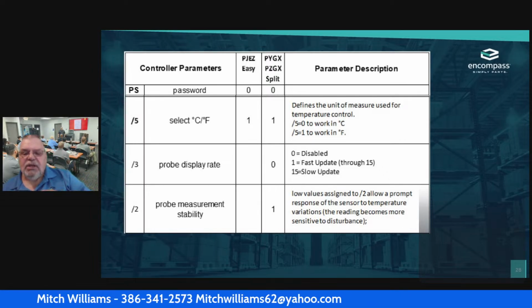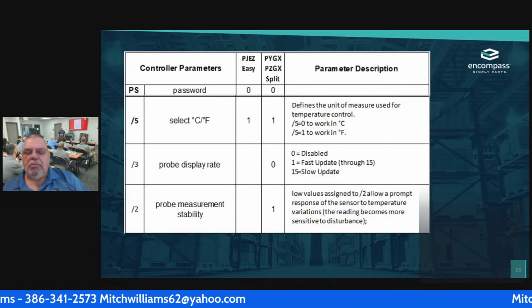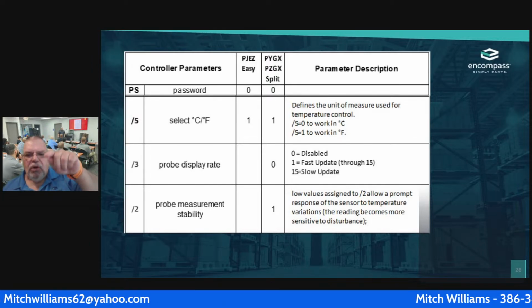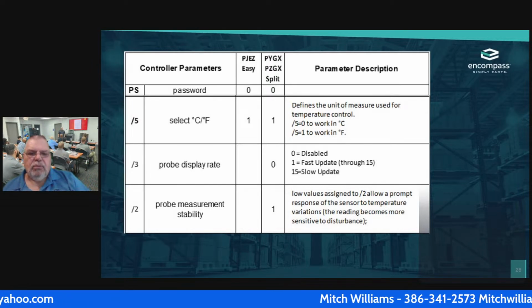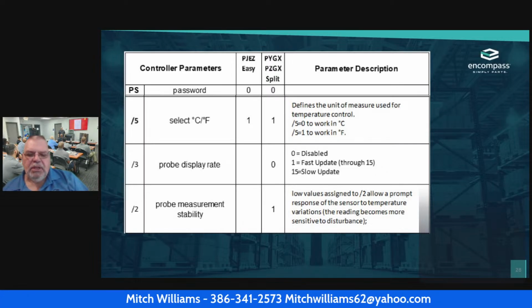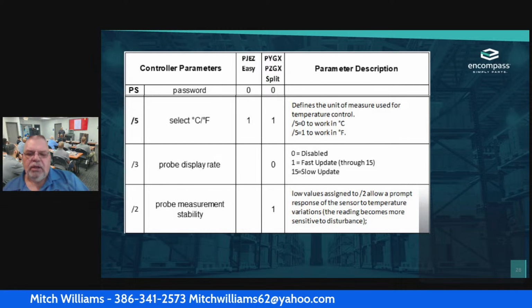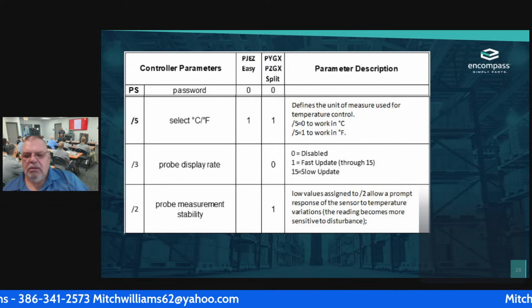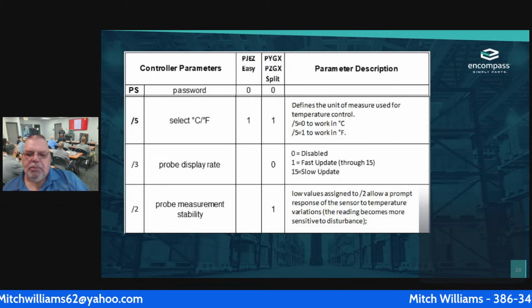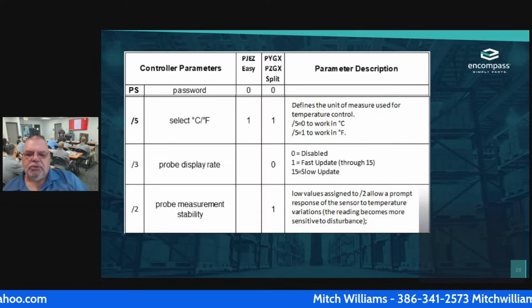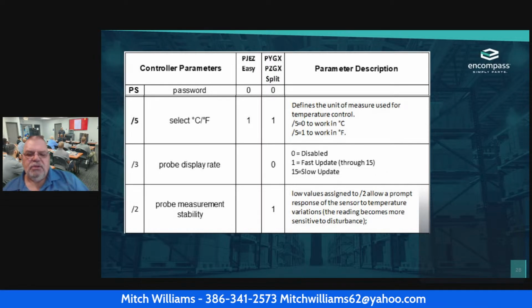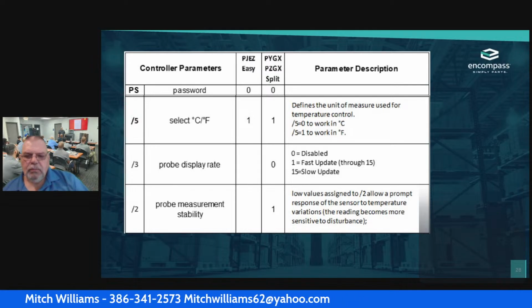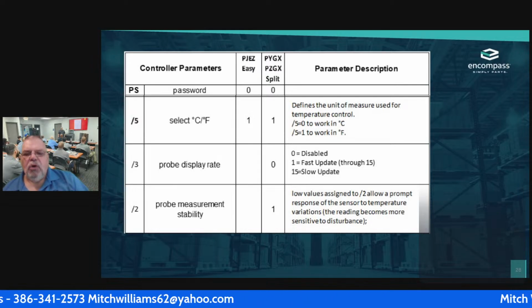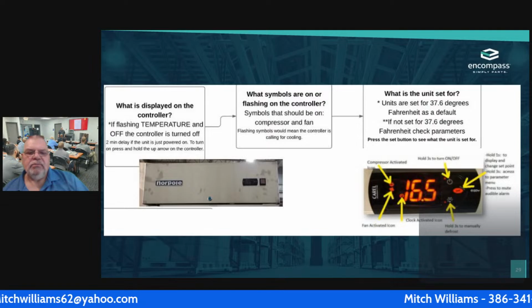1 is a fast update, and 15 is a slow update. I can go from 1 to 15, so I can just go through those. My probe measure stability, it's all set at 1. Low values assigned allow the prompt response of the sensor to the temperature variation. The readings become more sensitive to the disturbance. Okay, it's set up for 1. I can go 0 or 1.